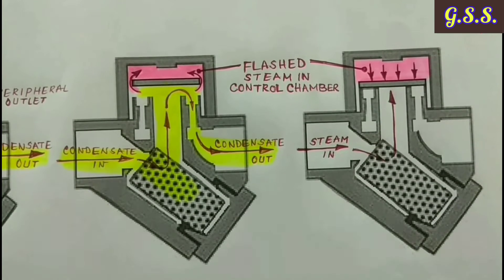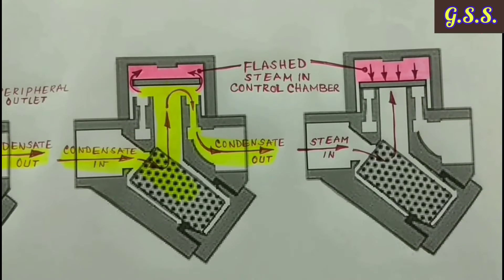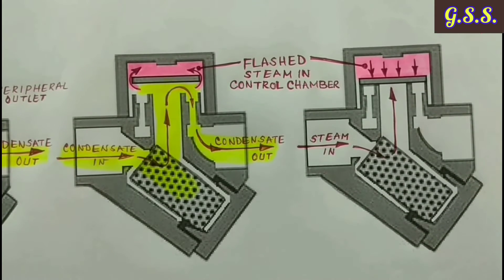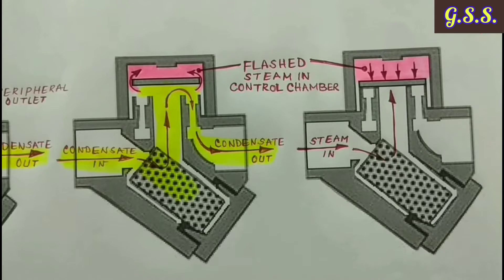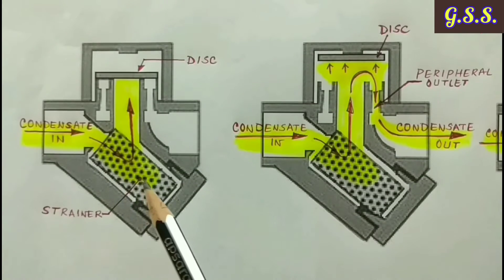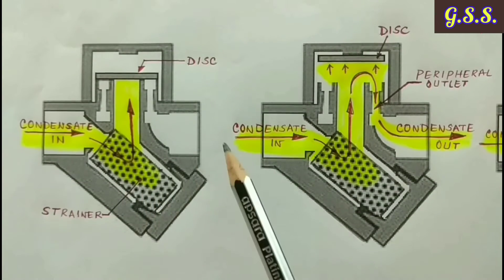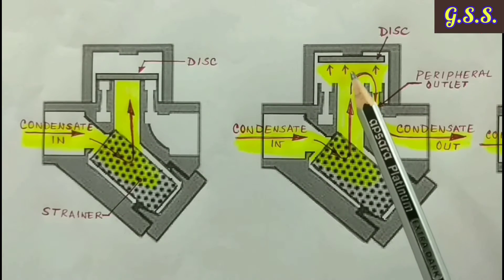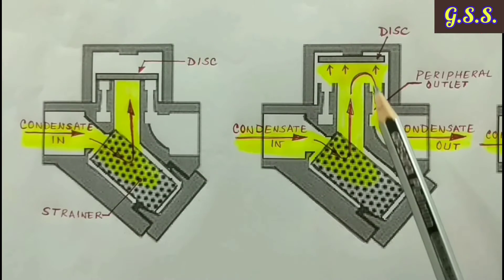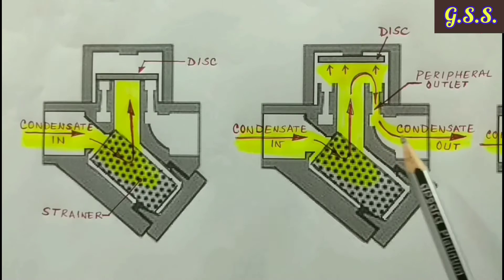After some time, the entrapped steam inside the control chamber gets condensed due to radiation heat loss and the cycle gets repeated. That means the incoming condensate again pushes the disc up and starts flowing out.